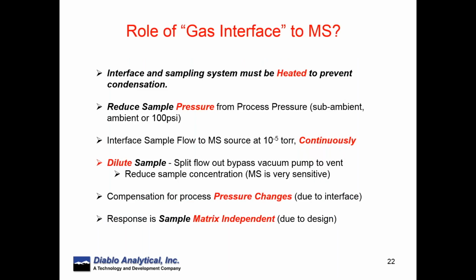In order to make all this work, it turns out that one of the most important parts of the system, besides having a very capable mass spectrometer, very reliable, very reproducible, and sensitive, is an interface, a gas interface that's properly designed. Much of the time when processes are hooked up, too much sample is provided to the mass spec, and so the mass spec is always working on the edge of saturation.